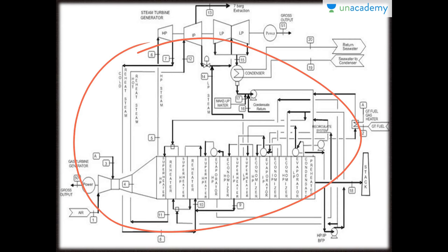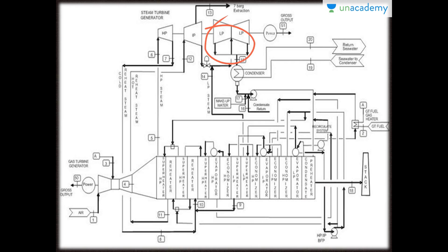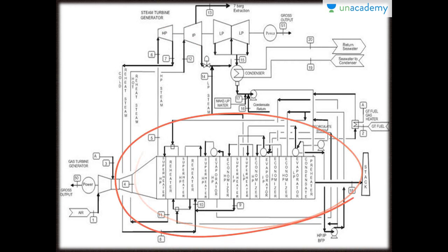Steam from the low pressure boiler is directed to the low pressure stage of the turbine. Each boiler comprises the usual economizer, evaporator and superheater sections. By comparing these figures, the temperature difference between the gas side and the steam side in the dual pressure cycle is considerably smaller than in the single pressure cycle. This gives the dual pressure cycle a considerable thermodynamic advantage: the smaller the temperature difference between the two streams for a given heat transfer rate, the smaller the degree of irreversibility external to the steam cycle, and hence the greater the amount of work that may be produced.